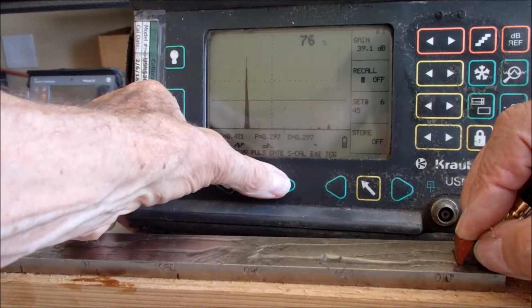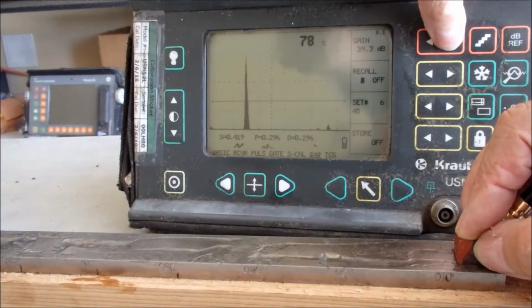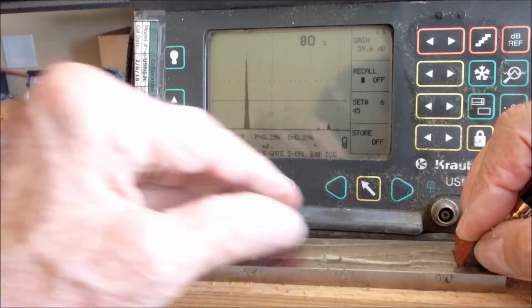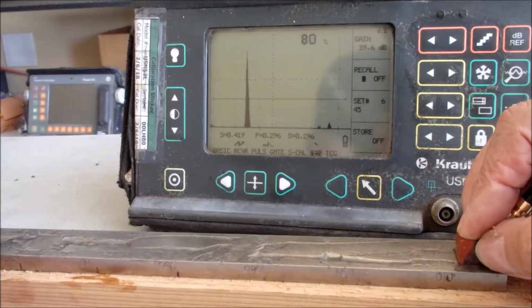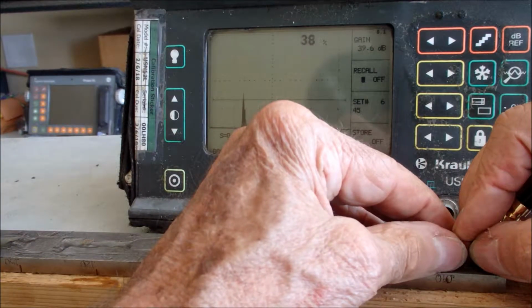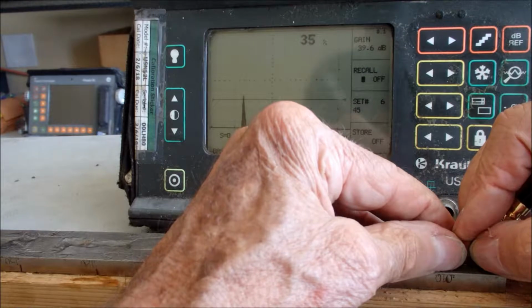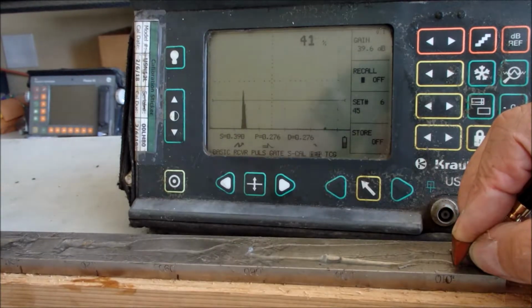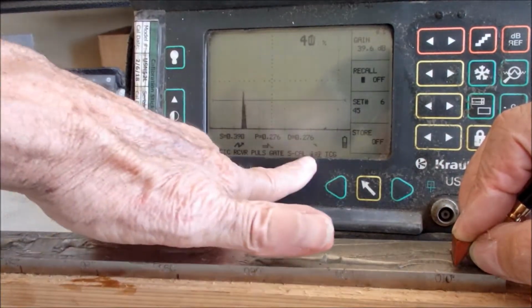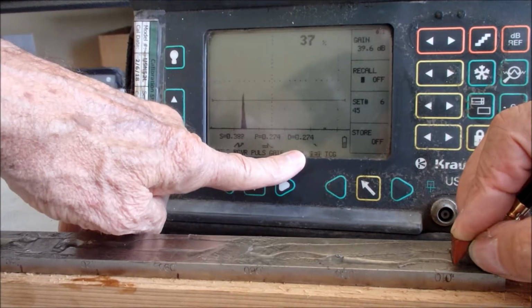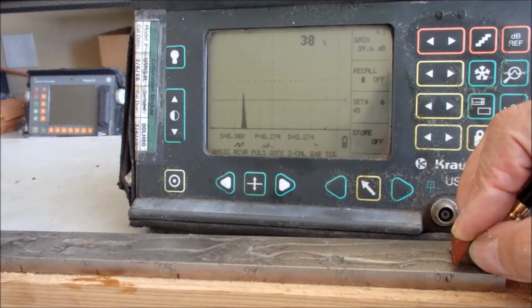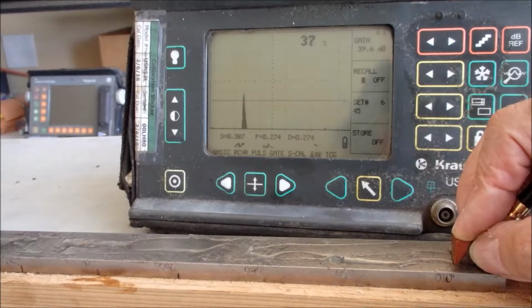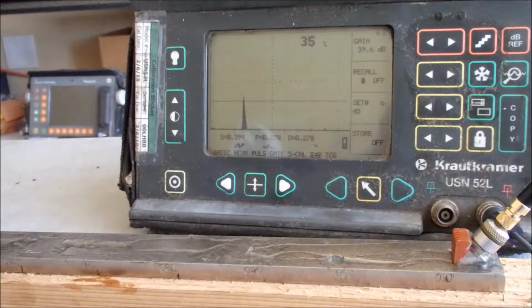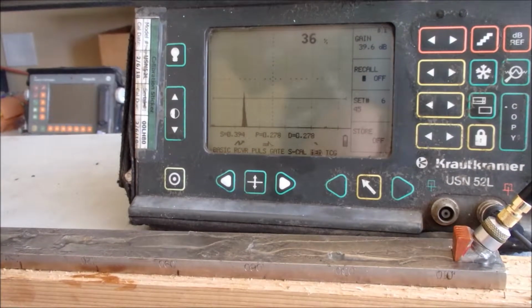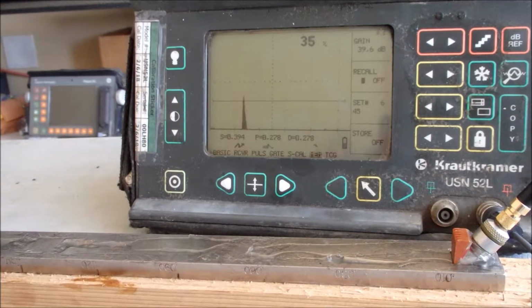And let's get this to read in percent. There's 80%. Now I'm going to move forward until it's 40% screen height. That'll be 6 dB less. 6 dB drop measurement. Should be right about there. All right, and our depth measurement is 276. 276 from 300 is 24 thousandths. So I'm going to say that's measured as 24 for a flaw height of 24 thousandths.